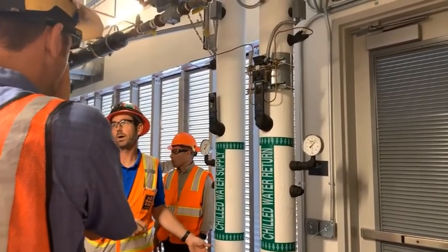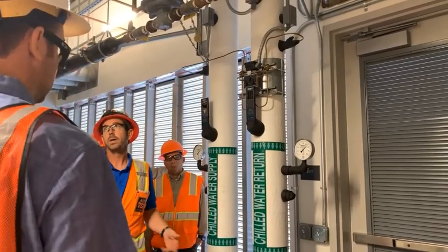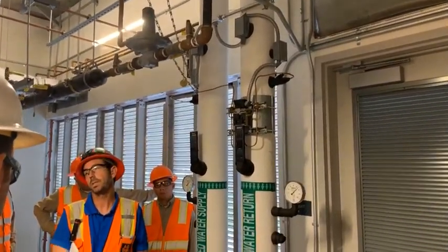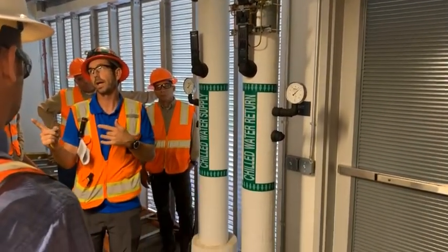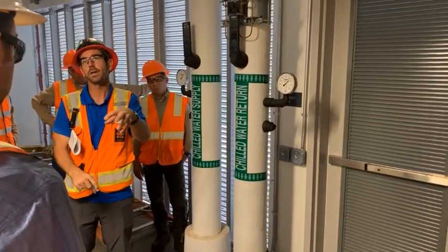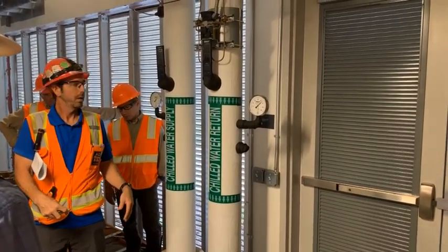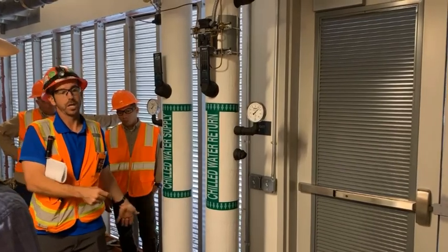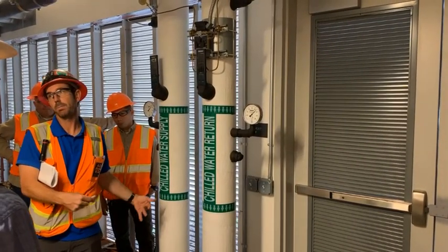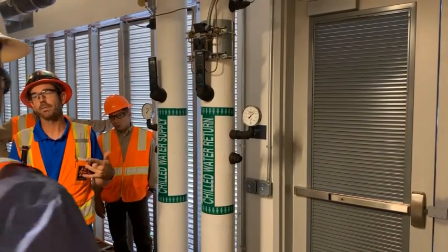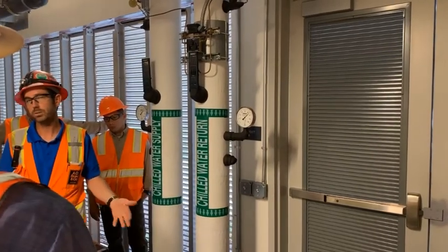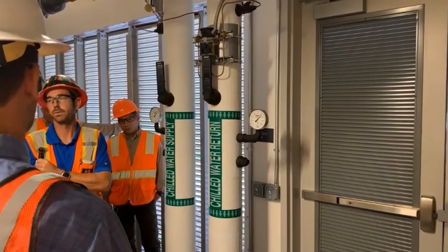The campus chilled water. Some of the IDFs have fan coils, and some of the IDFs are fed off of the air handlers. A straight cold tap off the air handler. Okay? So just know that if you shut the chilled water down, we need to get some temporary cooling devices over here for the IDF rooms, okay? Like MovinCool or something like that for the electric and IDF rooms. Okay?